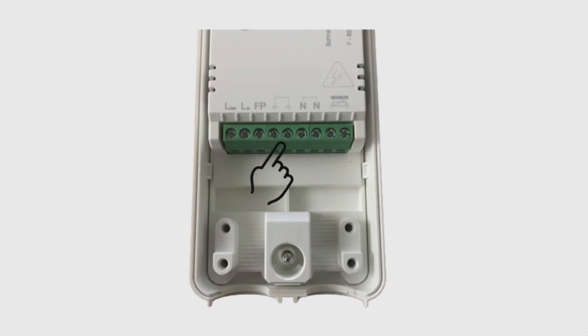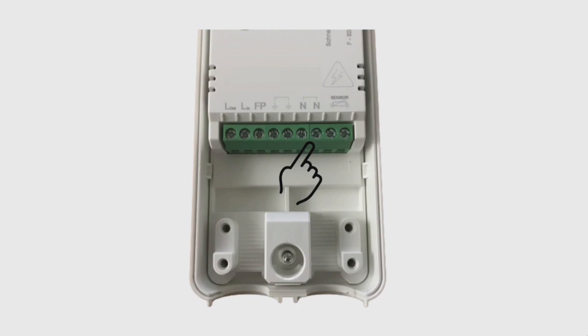There are two earth terminals which are linked together to maintain earth continuity on class one devices. A similar principle for the two neutrals - they're unswitched so connected to the two terminals that are internally linked. This makes the Wiser electrical heat switch a single pole single throw switch.